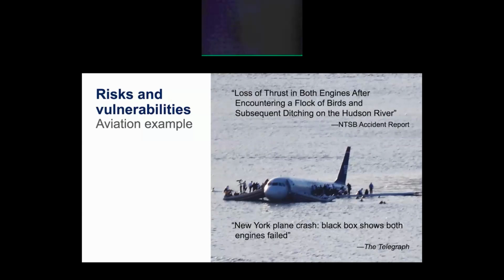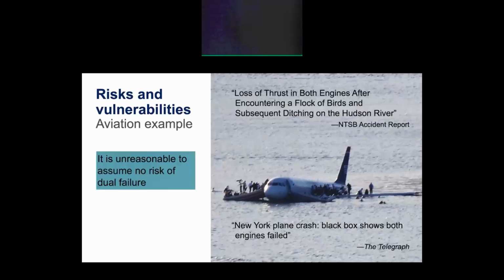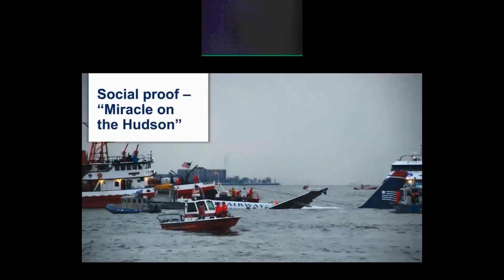Aerospace and aviation control systems historically share a lot of similarities with both the design and the failure of energy control systems. And although the N-2 condition of multiple bird strikes is an unlikely or low probability condition during takeoff, in 2009, when US Airways Flight 1549 struck a flock of geese, they actually experienced a dual primary engine failure. We need to anticipate and avoid dual failures in the process bus as well.